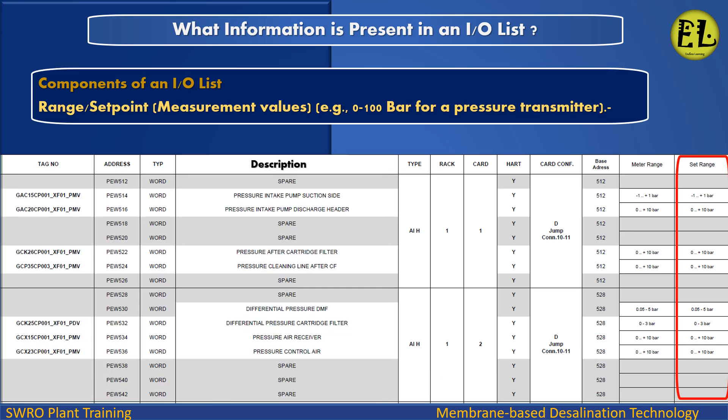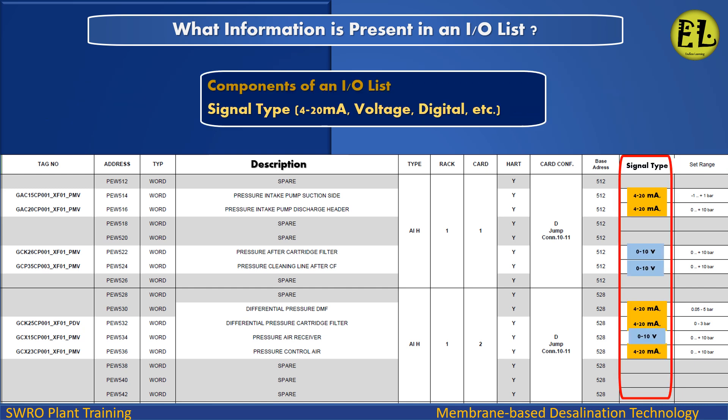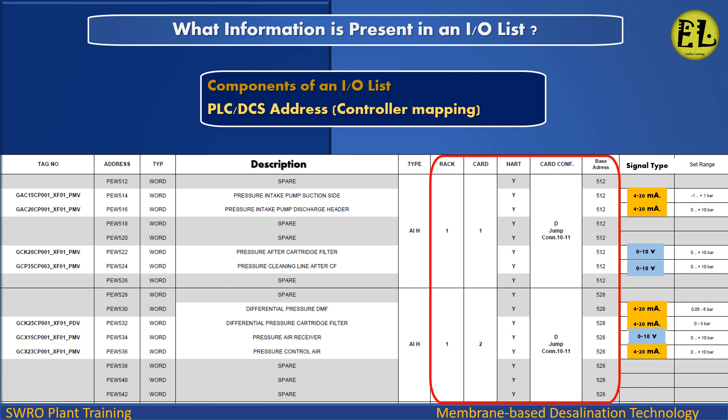Range / Setpoint: the measurement values, for example 0 to 100 Bar for a Pressure Transmitter. Signal Type: 4–20 mA, Voltage, Digital, etc. PLC / DCS Address: the controller mapping for each IO point.